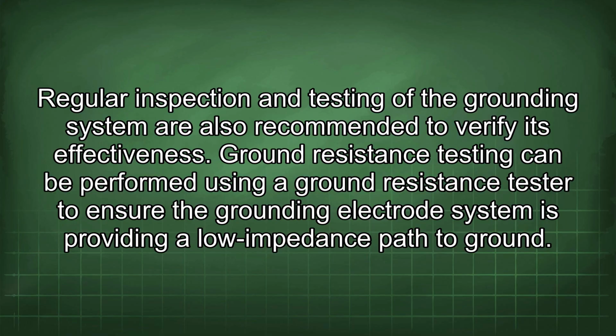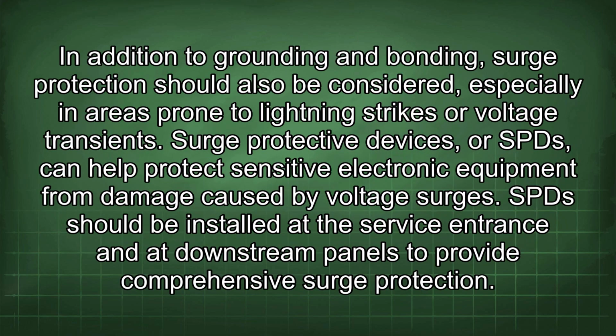Ground resistance testing can be performed using a ground resistance tester to ensure the grounding electrode system is providing a low impedance path to ground. In addition to grounding and bonding, surge protection should also be considered, especially in areas prone to lightning strikes or voltage transients. Surge protective devices, or SPDs, can help protect sensitive electronic equipment from damage caused by voltage surges. SPDs should be installed at the service entrance and at downstream panels to provide comprehensive surge protection.